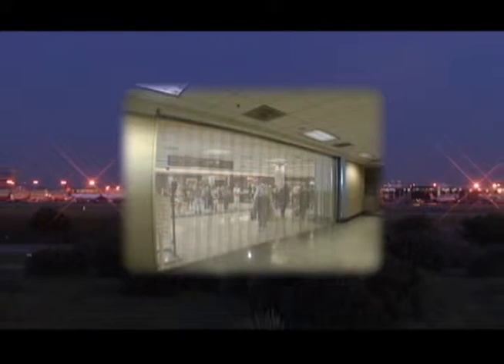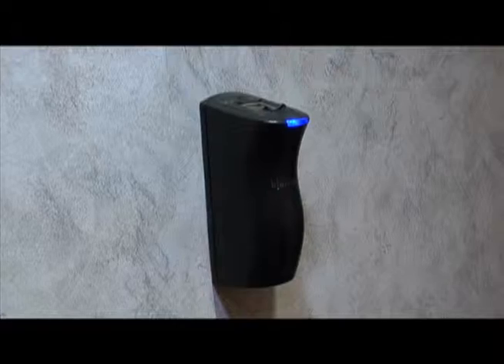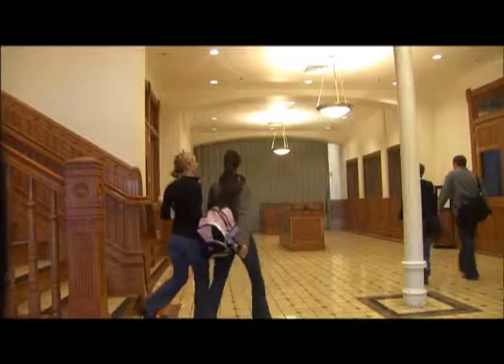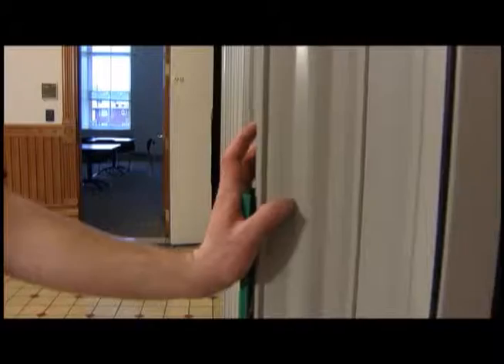In addition to providing fire and smoke protection, the door can also be used for access control. In this mode, the door assembly can be closed and locked in applications where this feature may be desired. The door can be operated and monitored remotely from a PC, or can be operated at the door location by key access, card readers, or other sophisticated means. Once the door enters the fire mode, the locking feature is disengaged, and the exiting feature is again activated.